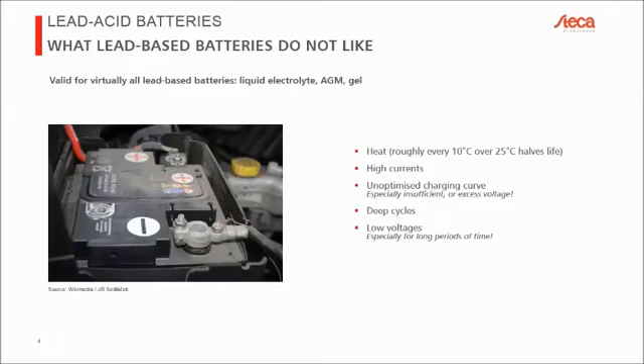You can even hear it when a battery is gassing when it's being overcharged. That's typically not good. It is okay, and it's actually important for a certain period of time, but if you were to do that every day, your battery would simply be dry at some point, and if you don't refill electrolyte, it will die. In the case of an AGM or gel battery, these are both closed battery types where you cannot refill electrolyte. In those cases, the battery will simply be dead, and there's nothing you can do about that.